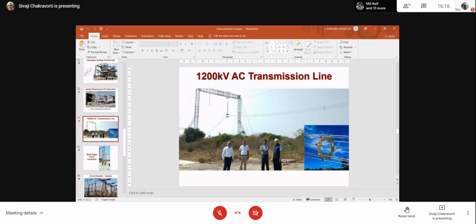Whereas here, see the effective diameter has increased significantly, quite large, so that the corona will be reduced, because corona depends on the effective diameter of the conductor. So by means of this bundle conductor, we have reduced the corona, and at the same time the current carrying capacity has been increased. Never confuse between bundle conductor and twisted conductor.